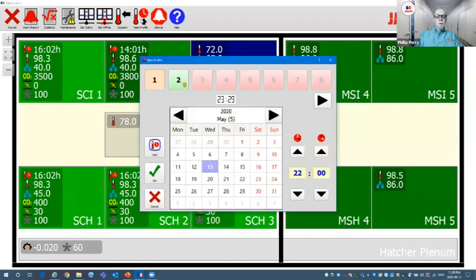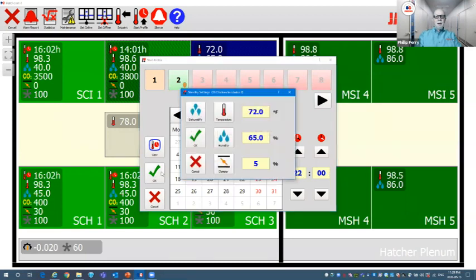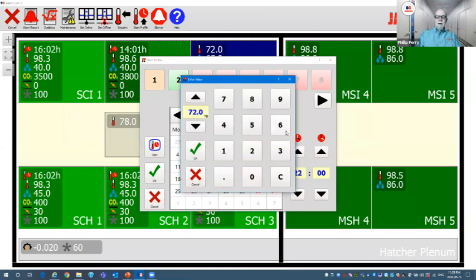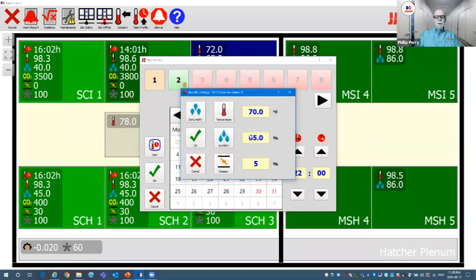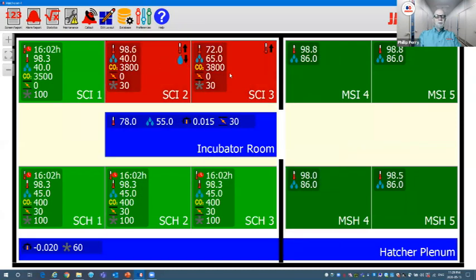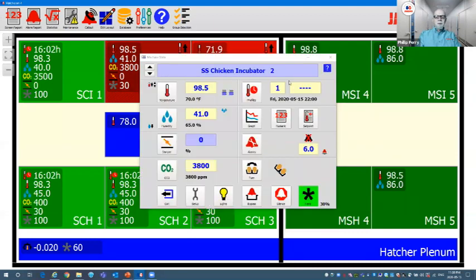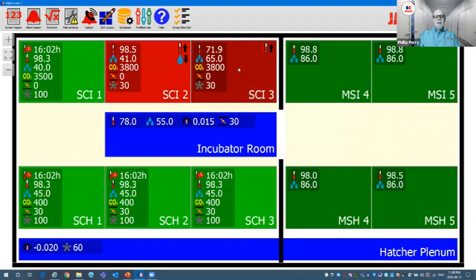And then we're going to start a profile on these. We're going to select two. These are going to be set on Friday. We're going to set them at 2200 hours. We would say okay. It would have our standby settings. Let's say we want to hold them at 70 until the profile starts, 65 humidity, 5% damper, say okay. And then these two machines are now in alarm, but we have changed both of these, and they are running on the same standby setting currently. And we changed them all. So again, a very cool group setting. I'm going to change these back.